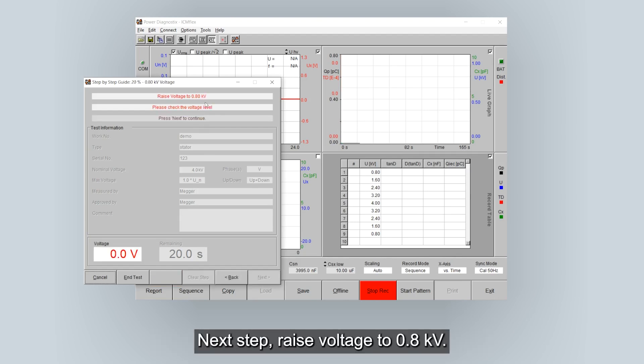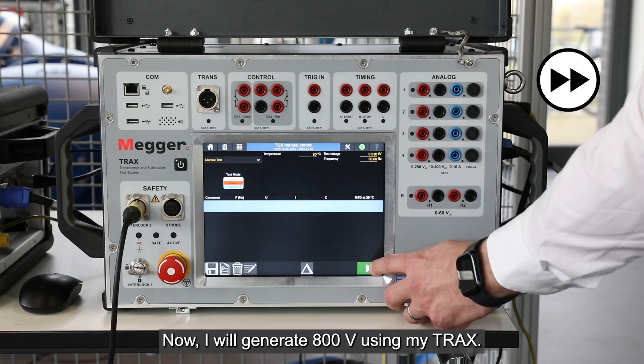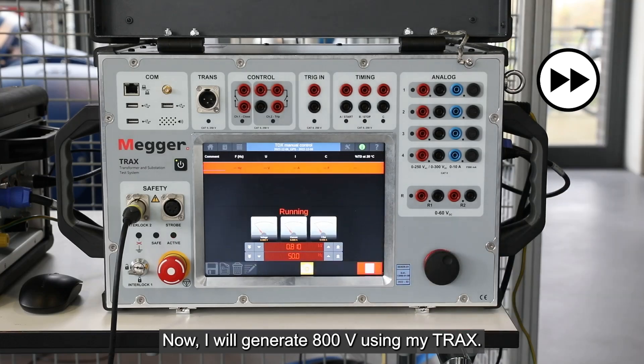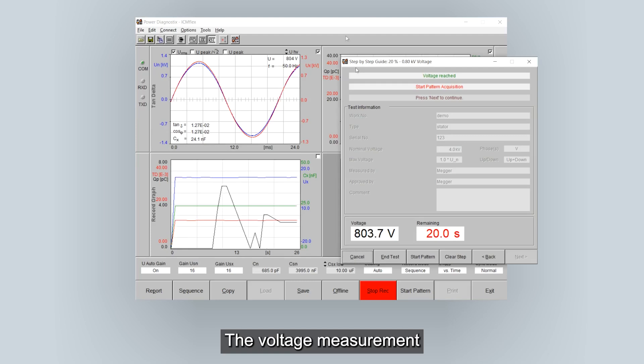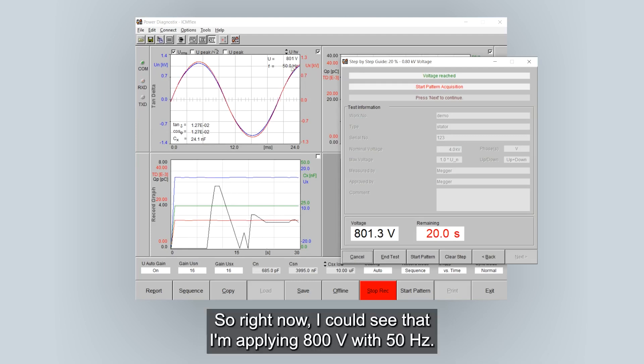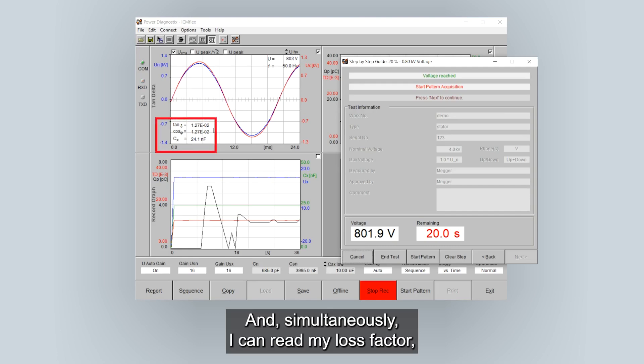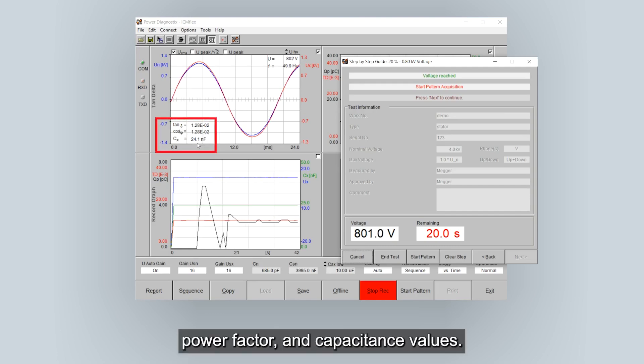Next step, raise voltage to 0.8 kV. Now I will generate 800 volts using my Trax. The voltage measurement path of the ICM Flex is calibrated. So right now I could see that I'm applying 800 volts with 50 hertz and simultaneously I can read my loss factor, power factor and capacitance values.